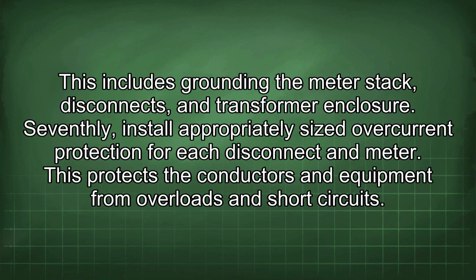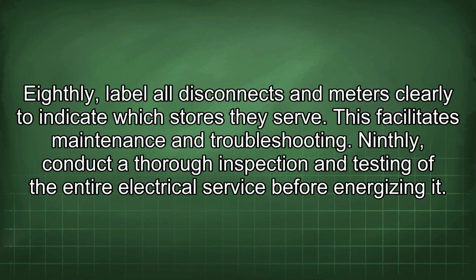This includes grounding the meter stack, disconnects, and transformer enclosure. Seventhly, install appropriately sized overcurrent protection for each disconnect and meter. This protects the conductors and equipment from overloads and short circuits. Eighthly, label all disconnects and meters clearly to indicate which stores they serve. This facilitates maintenance and troubleshooting.